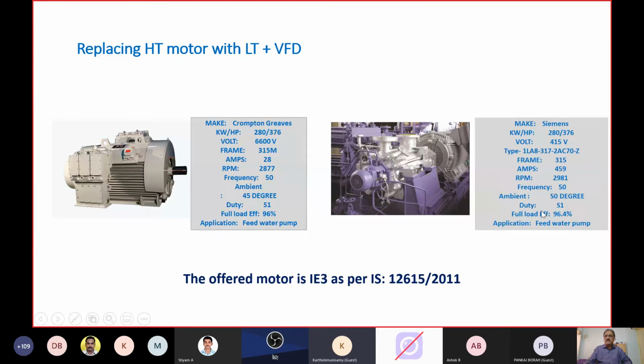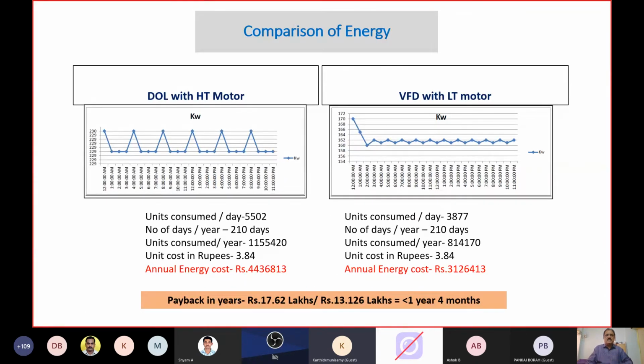So we gave a calculation, we convinced the management, and 3 boiler feed pump motors were replaced in one shot using this method. This is a slide I borrowed from the senior manager of engineering from that group, a sugar mill, which he had used for his MTech course, showing the units consumed and energy saving achieved by converting the HT motor to an LT motor. The bottom line is they achieved a payback of less than 2 crushing seasons.